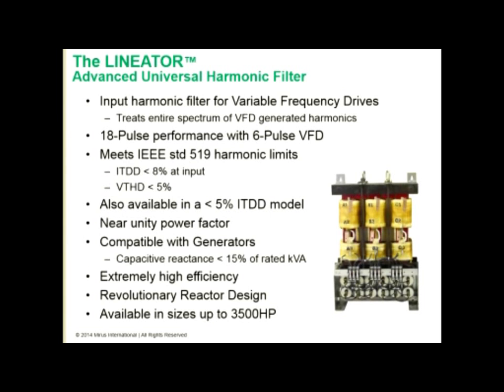We have extremely high efficiency, so the highest efficiency of all filters in the market, and higher efficiencies than other forms of treatment, such as transformers used for phase shifting, for multi-pulse systems, or active front-end drives, or parallel active filters. The key is in the design of our reactor. It's a very unique reactor, which allows us to keep the capacitor bank small and get the high level of performance. And there are sizes up to 3,500 horsepower available.